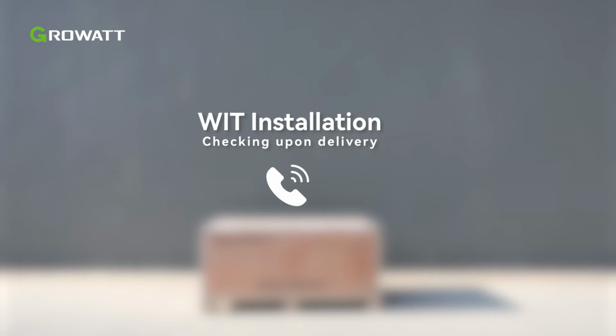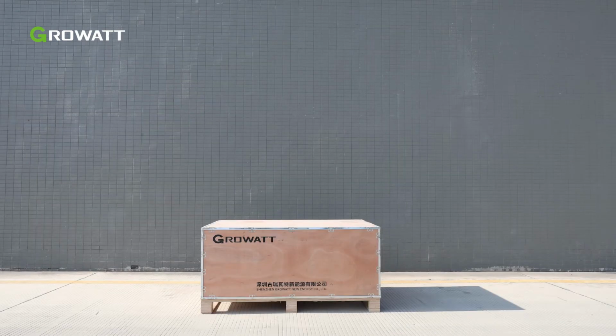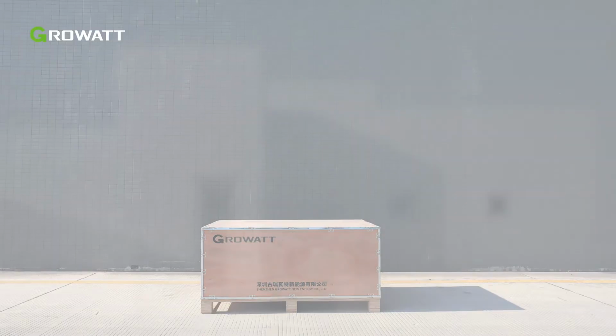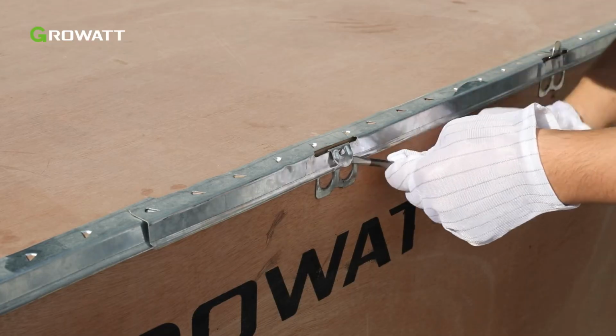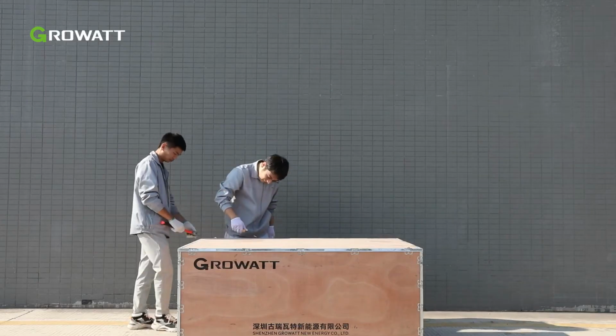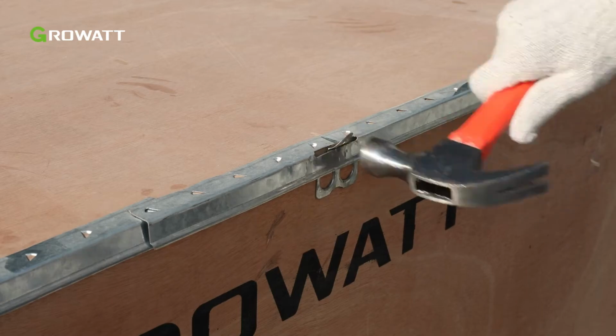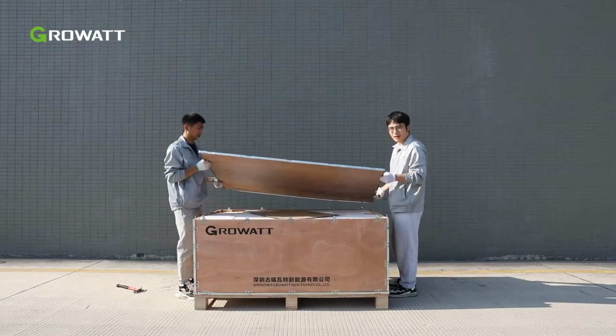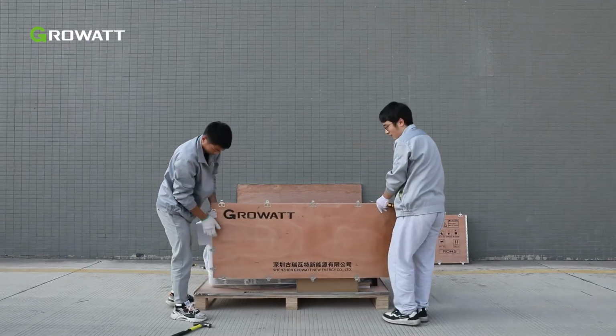Before unpacking the WIT inverter, check the shipping box for any externally visible damage. If any damage is found, please contact the shipping company as soon as possible. The WIT inverter is securely packaged in a wooden container. First, we need to use a flathead screwdriver and hammer to loosen the metal fasteners on each cover. Remove the top cover first and then the other covers.